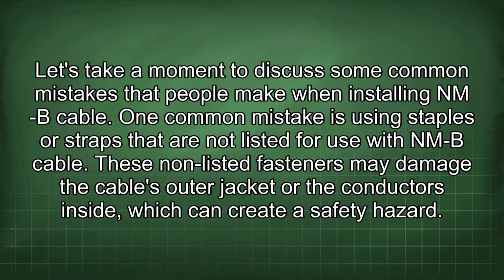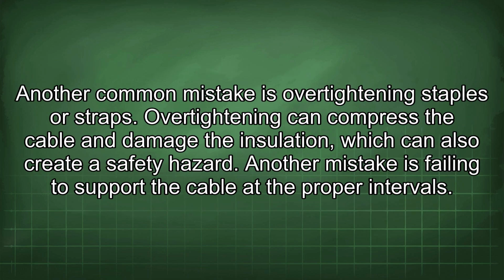Let's take a moment to discuss some common mistakes that people make when installing NMB cable. One common mistake is using staples or straps that are not listed for use with NMB cable. These non-listed fasteners may damage the cable's outer jacket or the conductors inside, which can create a safety hazard. Another common mistake is over-tightening staples or straps. Over-tightening can compress the cable and damage the insulation, which can also create a safety hazard.